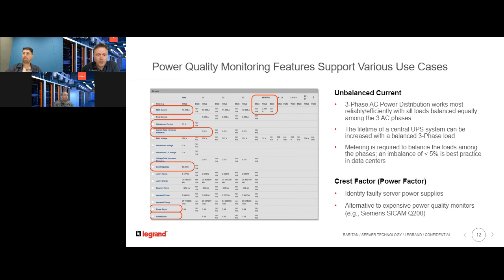The measurement of unbalanced current inside a three-phase power distribution system is a very important feature because the phase with the highest load, of course, physically defines the maximum required backup capacity of your three-phase UPS in your data center. And if the phases are not equally loaded on the UPS, its lifetime can be affected negatively. A typical rule of thumb for a three-phase AC distribution system in a data center says that the imbalance between the phases should not exceed more than 5%.